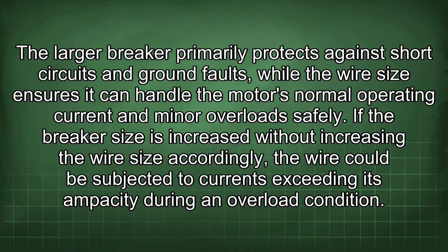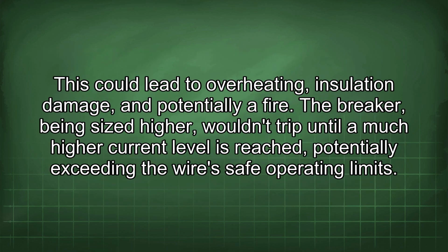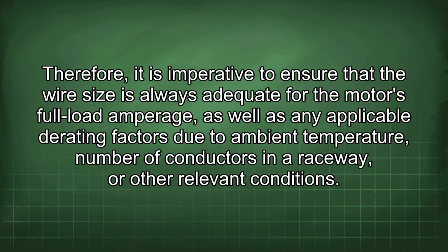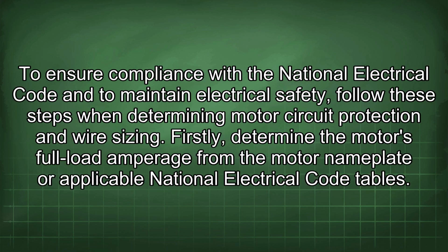The larger breaker primarily protects against short circuits and ground faults, while the wire size ensures it can handle the motor's normal operating current and minor overloads safely. If the breaker size is increased without increasing the wire size accordingly, the wire could be subjected to currents exceeding its ampacity during an overload condition. This could lead to overheating, insulation damage, and potentially a fire. The breaker, being sized higher, wouldn't trip until a much higher current level is reached, potentially exceeding the wire's safe operating limits. Therefore, it is imperative to ensure that the wire size is always adequate for the motor's full load amperage, as well as any applicable derating factors due to ambient temperature, number of conductors in a raceway, or other relevant conditions. To ensure compliance with the National Electrical Code and to maintain electrical safety, follow these steps when determining motor circuit protection and wire sizing.